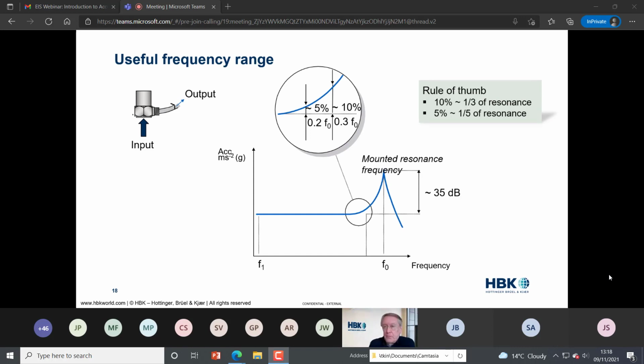So the rule of thumb generally used in deciding which accelerometer is suitable for a measurement where you have a particular frequency range requirement is that you can measure up to 1/3 of the resonant frequency. So if an accelerometer has a resonant frequency of 30 kilohertz, you can safely measure up to around about 10 kilohertz. If you go beyond 10 kilohertz in that case, you run the risk of exciting the resonance, which will give you wrong and overloaded results. So that's something important you have to bear in mind.